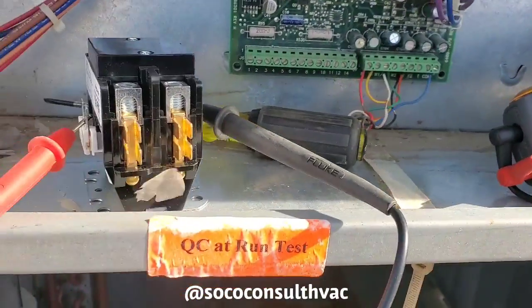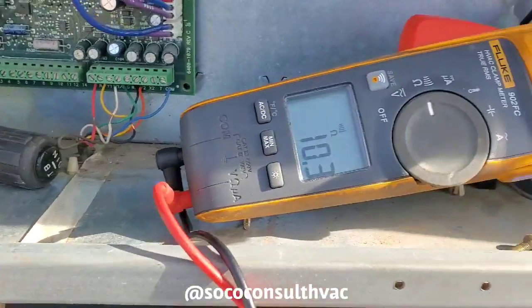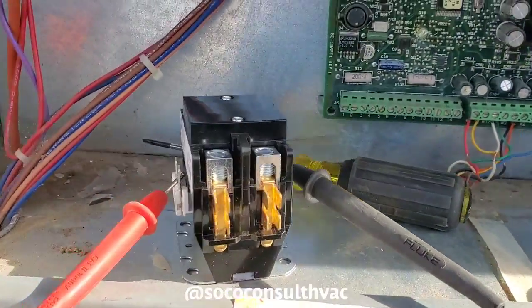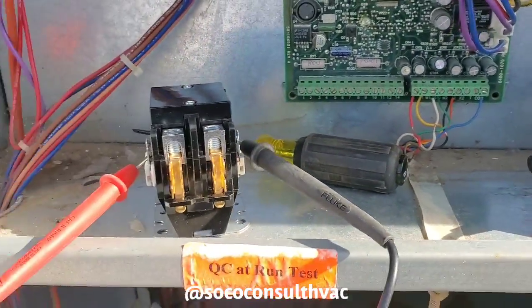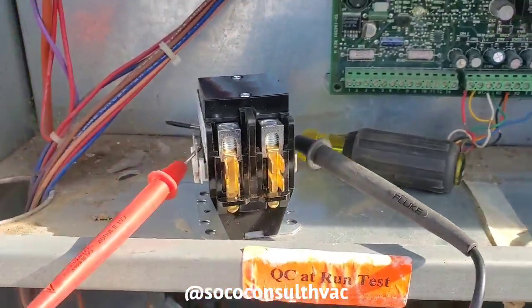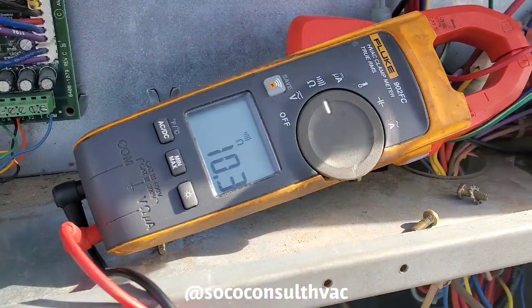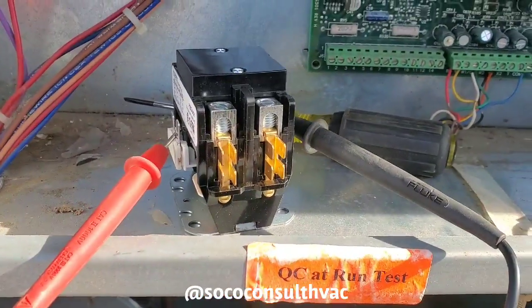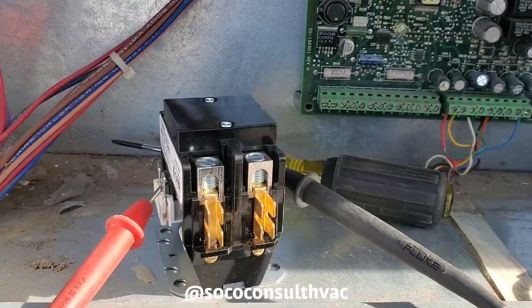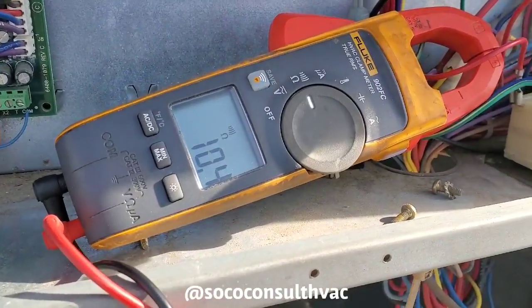So kind of store that in the back of your mind if you're ever suspecting that a contactor is starting to go bad. It might be chattering, it might be blowing fuses every now and then. Now obviously, not every contactor is going to ohm out exactly 10 ohms. A larger contactor is going to have more of a coil on it, so it needs a bigger magnet to pull those contacts in, so it's probably going to ohm out more.